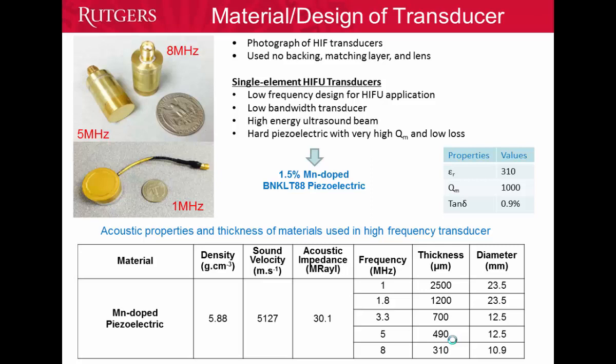Until now, most HIFU transducers are made with lead-based compositions, but here we chose a lead-free material, bismuth sodium titanate with 1.5% manganese dope. These transducers are single element transducers. We didn't use any backing layer, and we didn't use any kind of focusing technique.